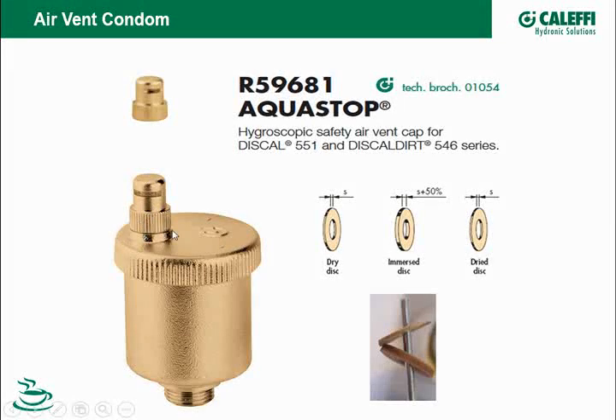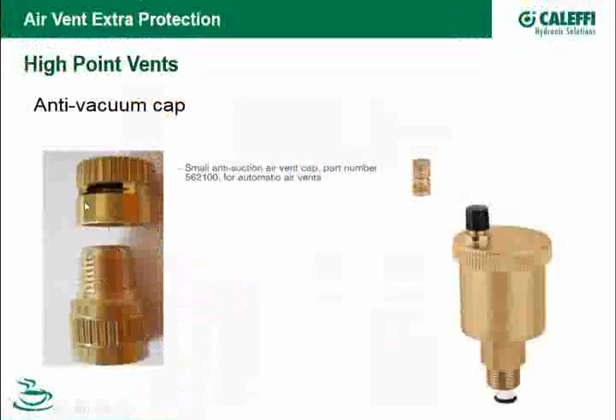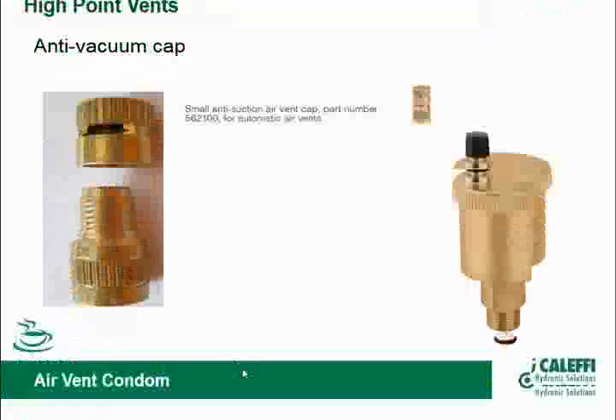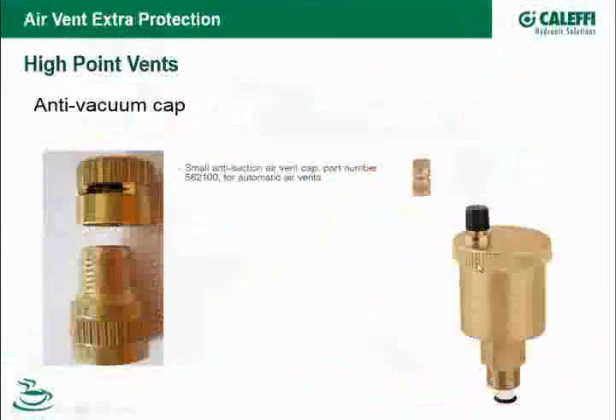Again, it does fit a lot of different brands. It's a common thread. You can actually use these in conjunction with one another. You can put one of the hygroscopic caps, or one of these AquaStop caps, I'm trying to say here, on top of the check valve. So now you've got the check valve, the AquaStop cap, as well as the float valve in here. So you've got a 3-in-1 device there.